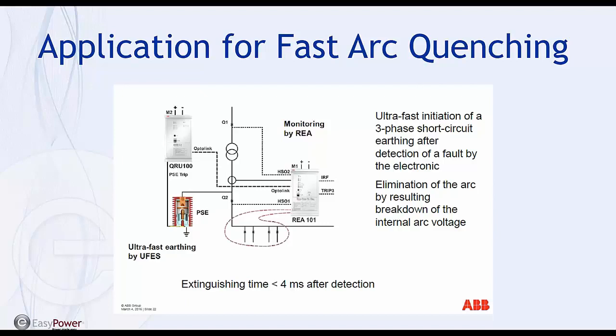There's essentially no damage whatsoever when things operate that fast. As a matter of fact, during human testing, the copper wire they used to create the 3-phase to ground fault didn't even melt completely before the REA arc flash system quenched the arc. So just to give you an idea how fast that is. And of course, the only downside is replacing the current limiting fuses, and you're putting a fault on your system. But with that amount of time, it's such a fast clearing time that it's not really a significant issue.